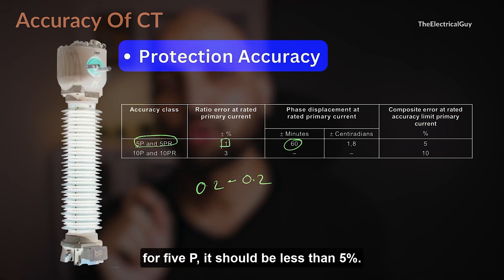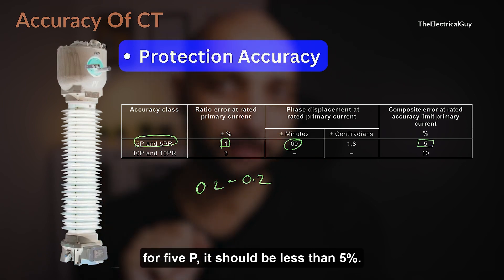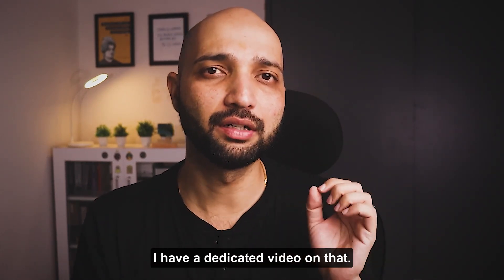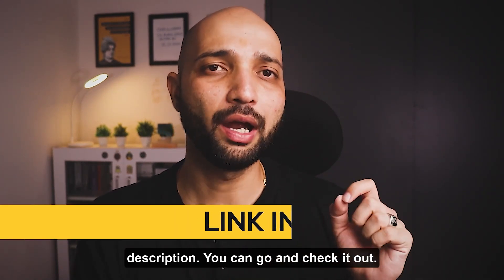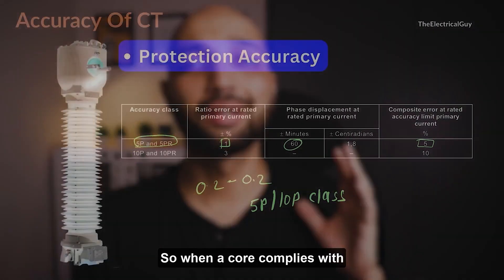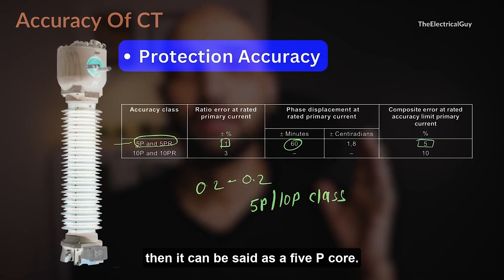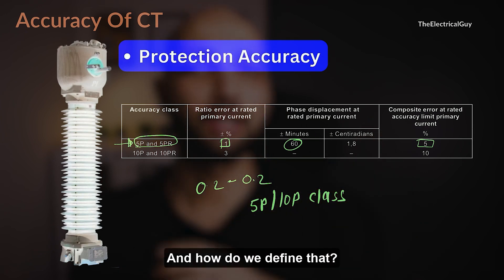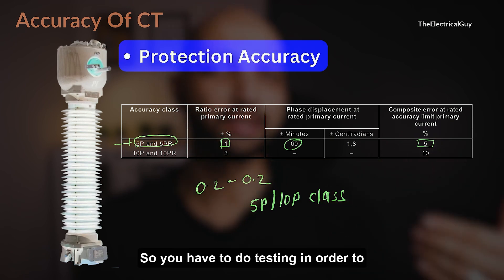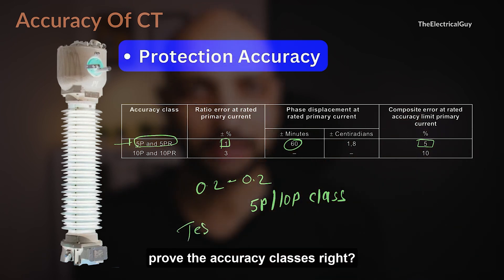For 5P, the composite error should be less than 5%. When a core complies with all these requirements, it can be said to be a 5P core. This is determined through testing — you have to do testing in order to prove the accuracy classes.